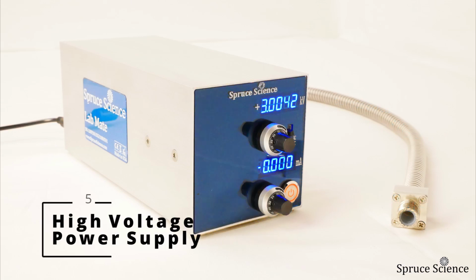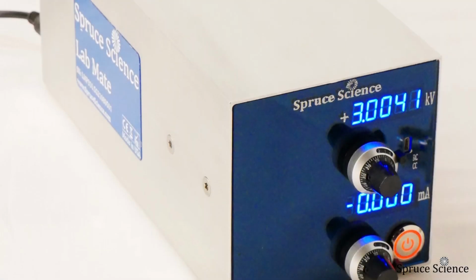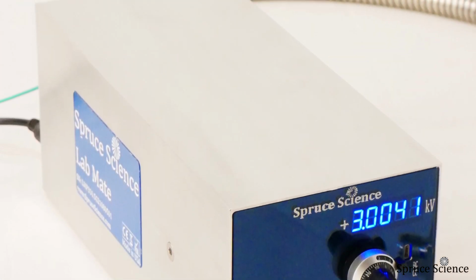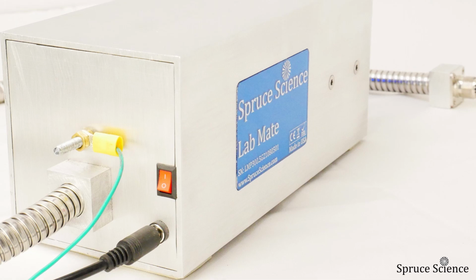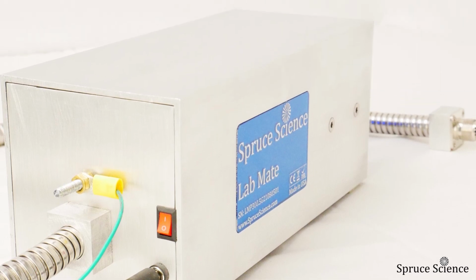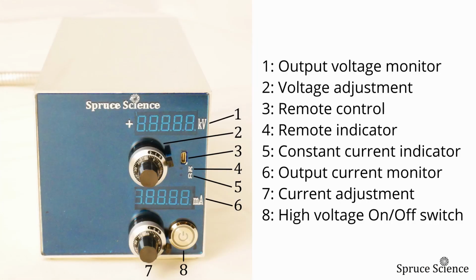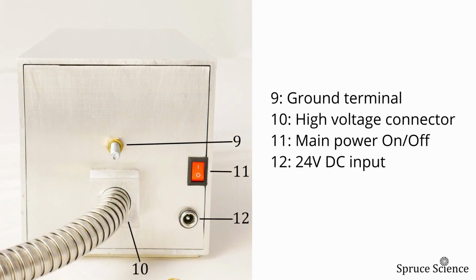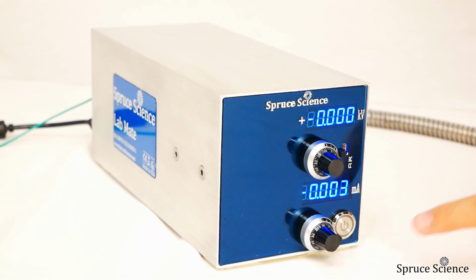The adjustable high voltage power supply is a key component of the electrospinning setup, giving you complete control over the output. You can switch between constant voltage mode and constant current mode to suit your specific needs. This particular model can deliver a powerful 30 kilovolts, which is a great range for electrospinning applications. The current output limit is 400 microamps, which is more than sufficient for the electrospinning process and ensures that you have a good fit for your application.